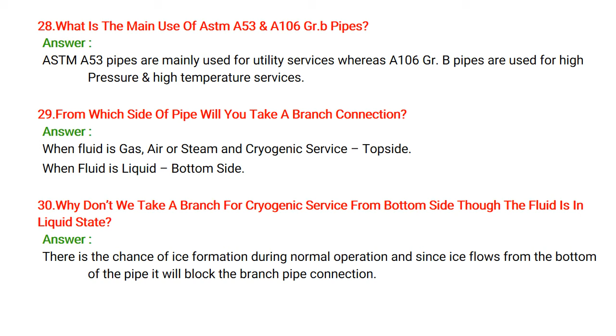Why don't we take the branch for cryogenic service from the bottom side, though the fluid is in liquid state? See, there is a chance of ice formation during normal operations, and since ice forms from the bottom of the pipe, it will block the branch connections.